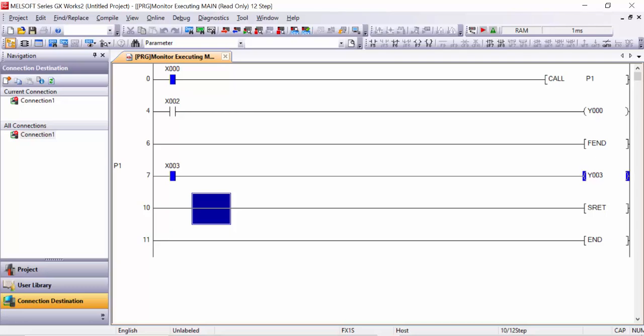If I remove the signal from X0 — now I have removed the signal. If I give the X3 signal again, the signal is coming but our output Y3 will not turn ON because the CALL to P1 is no longer active. So any program you write after P1 will only work when you give the signal to X0. You can use M0 internal memory or external hardware inputs as well.